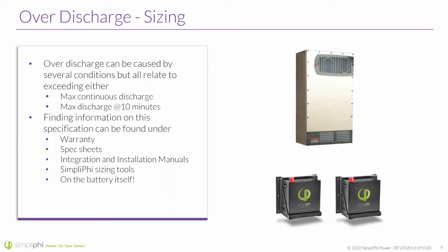We have tools. We have the sizing tool. We have both the one based on kilowatt hours, that's the more basic tool, but we also have a system sizing tool that incorporates the inverter you're using and the chargers you're using, and calculates out those minimum sizes. If you're looking for the specs on the battery themselves, right on the top of it, you will see these specs called out on max discharge. It is called out right on the battery, so you can't miss it when you're installing. It's right there in plain sight.